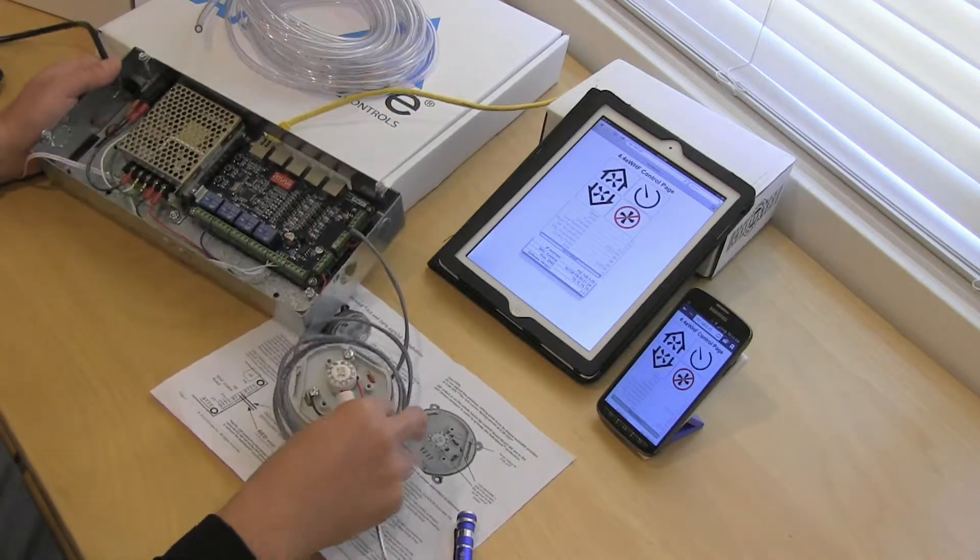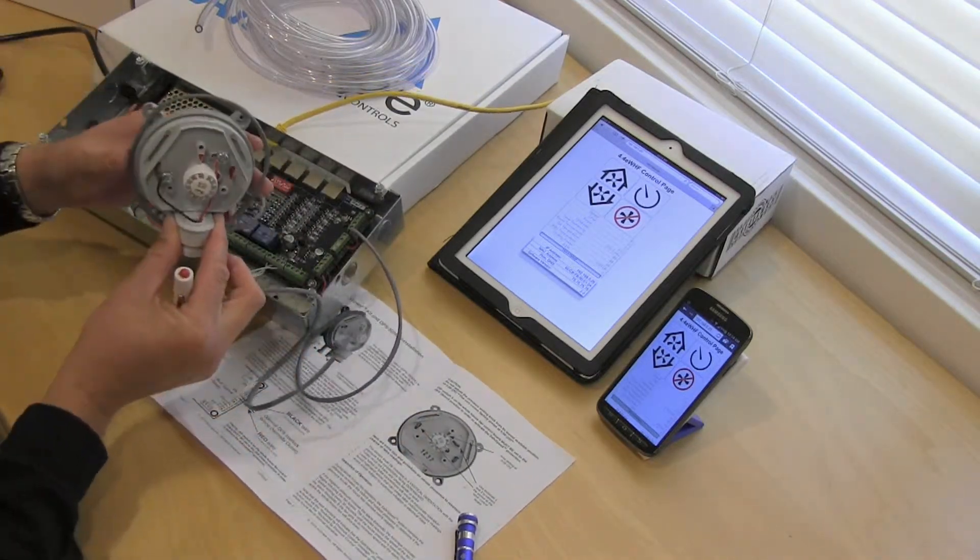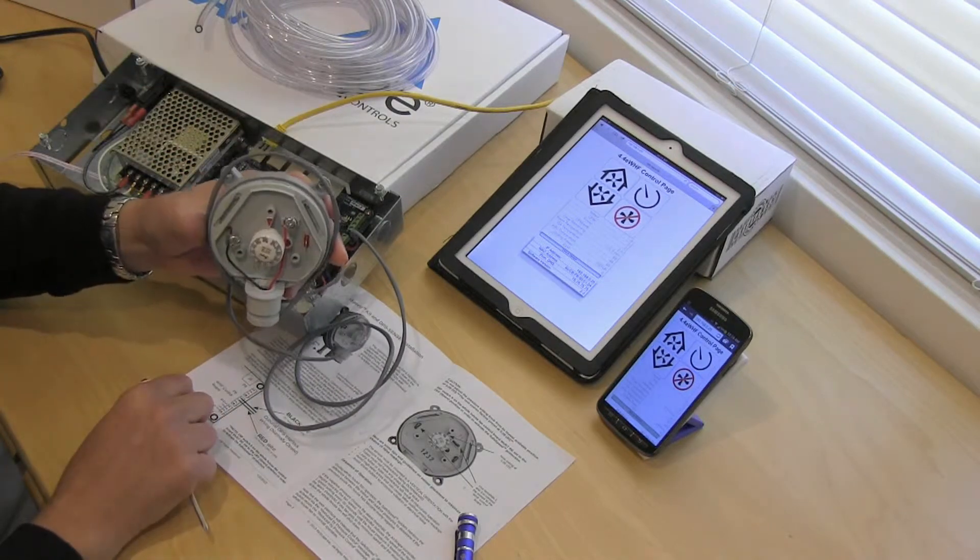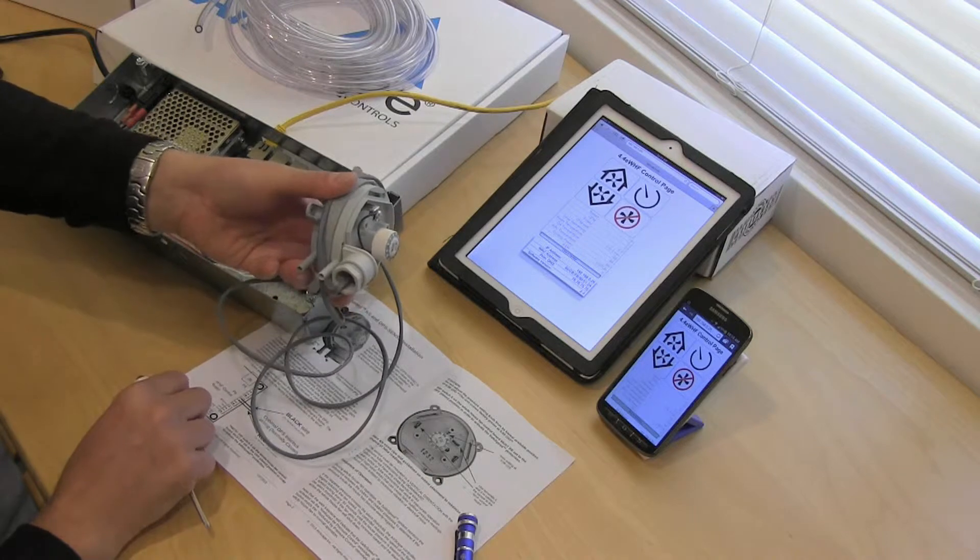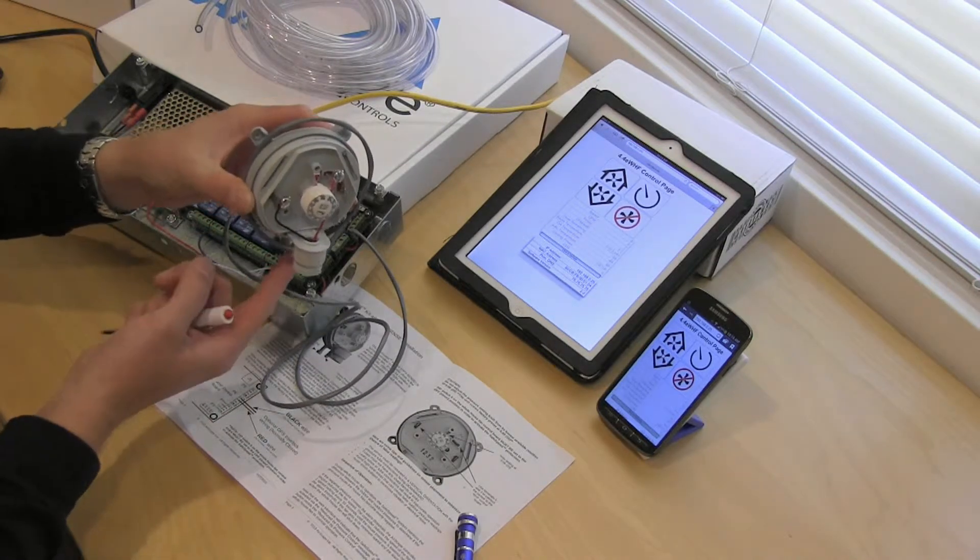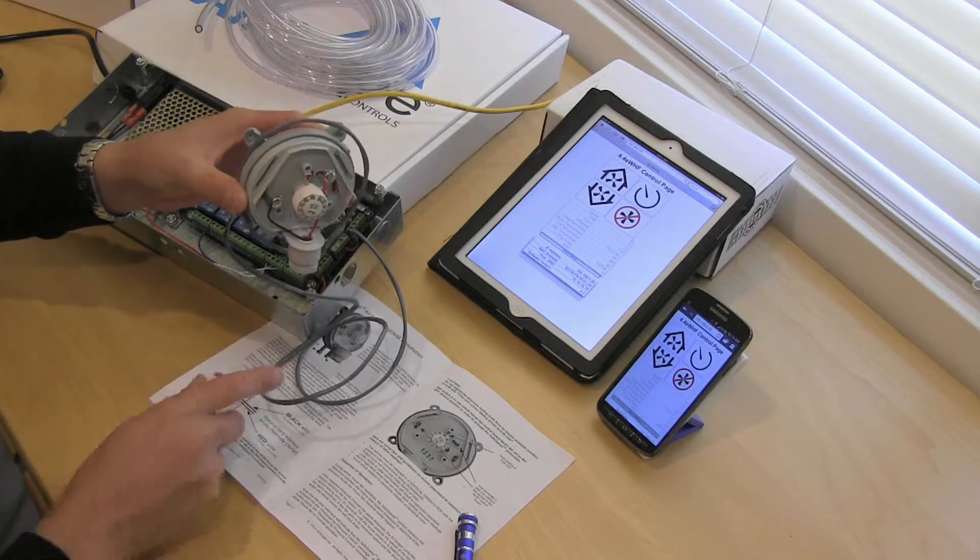Now let's talk about how to mount the sensor. You want to make sure it's mounted in a vertical orientation just like this. So it cannot be lying down, it can't be flipped sideways, it's got to be perfectly vertical with the ports, the connection ports facing downwards.